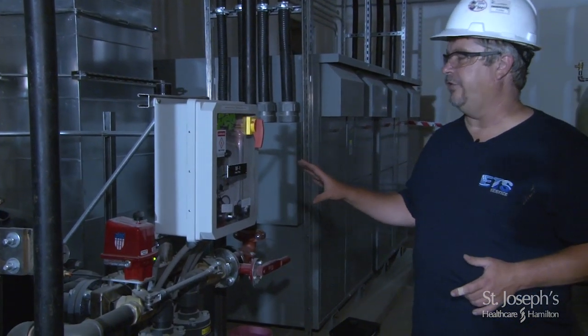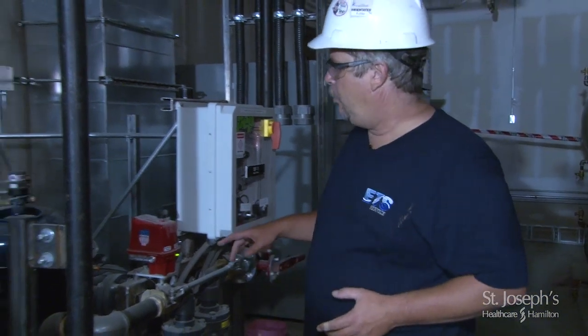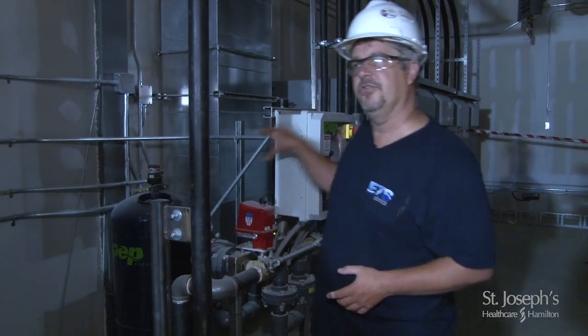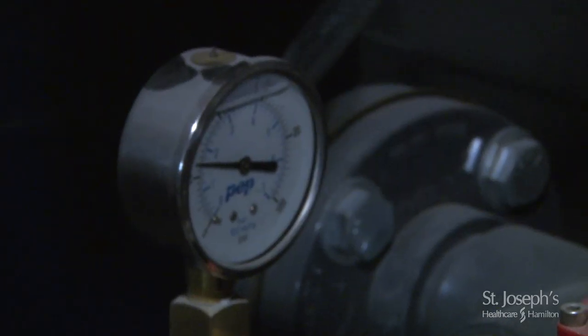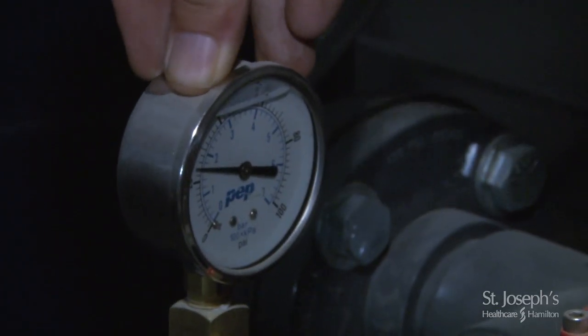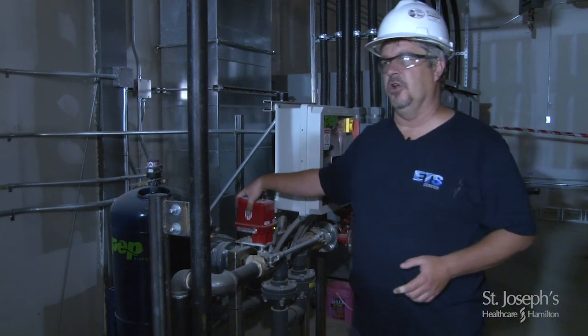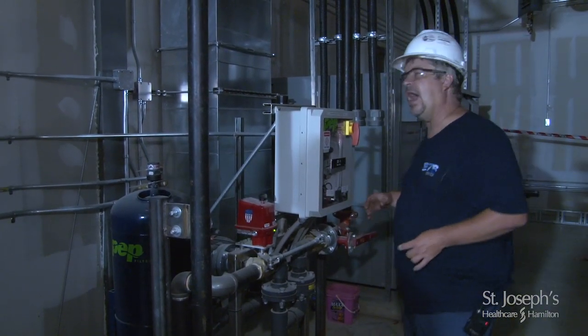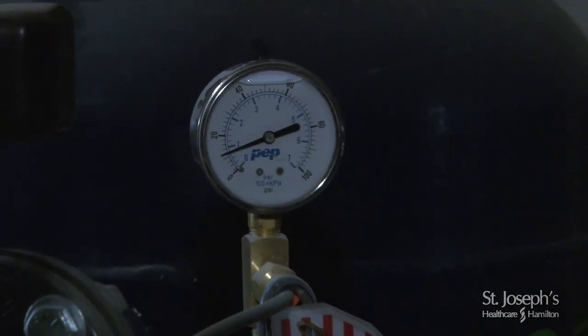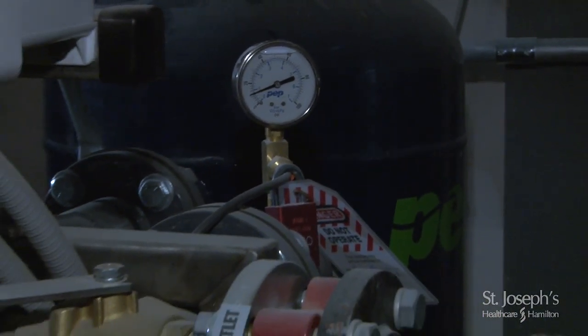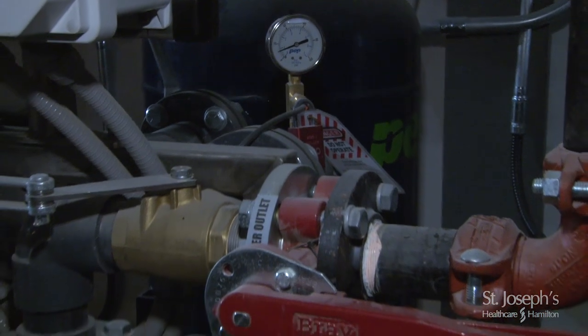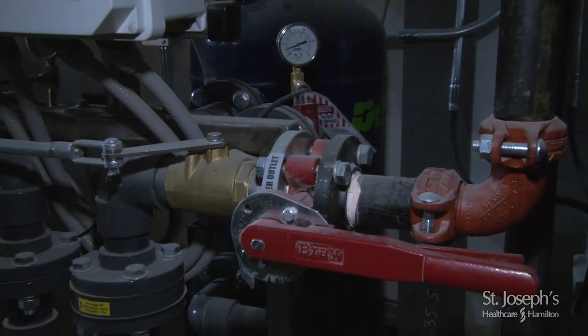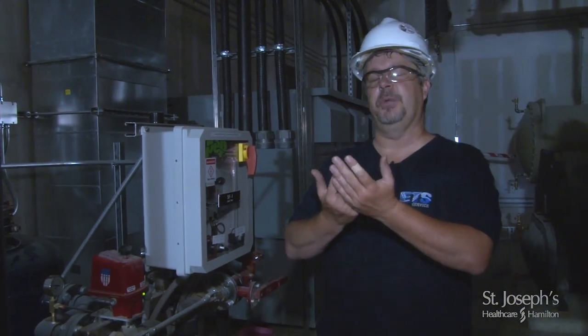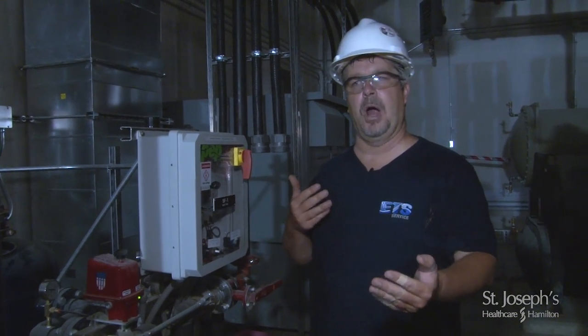How the filter works is we have pressure gauges that are monitored by this control panel. What it's looking at is the pressure incoming into the filter assembly, and at the same time it looks at the pressure of the water coming back out of the filter. As the filter is monitoring our incoming and outgoing pressures, and the filter gets a little bit dirty inside, the difference between the incoming and outgoing pressures will slowly grow further apart.